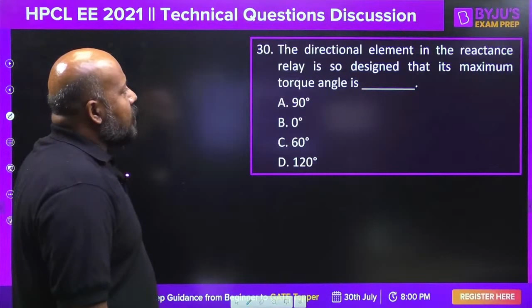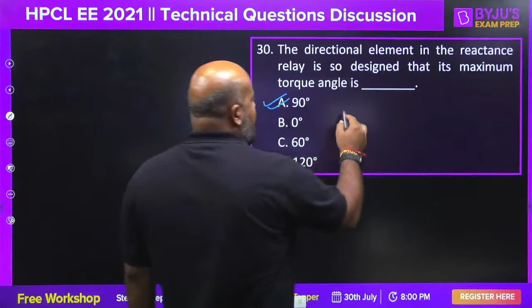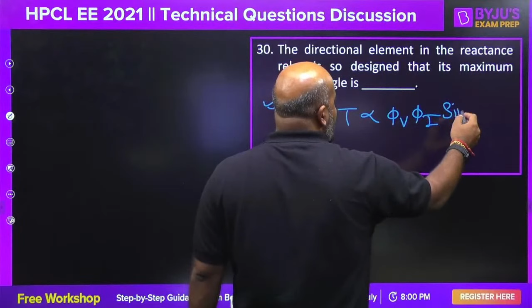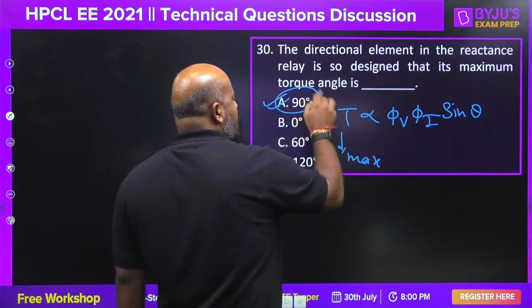The directional element in the reactance relay is designed so that its maximum torque angle is 90 degrees, because of the relation phi V, phi I, and sine of theta. So this torque is maximum when the angle theta is 90 degrees. That's the torque equation for the directional element.